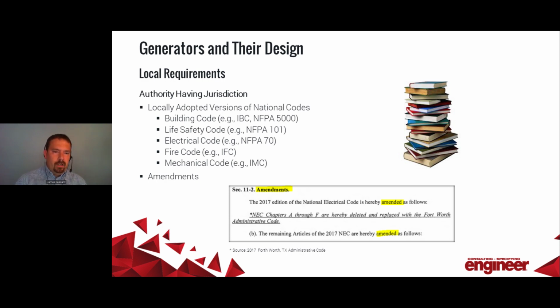Articles like 700 for emergency systems, 701 for legally required, 702 for optional standby, 705, 708. And then in the case of healthcare, where you've got Article 517 specific to healthcare installations, which also references NFPA 99, which is the code for healthcare.